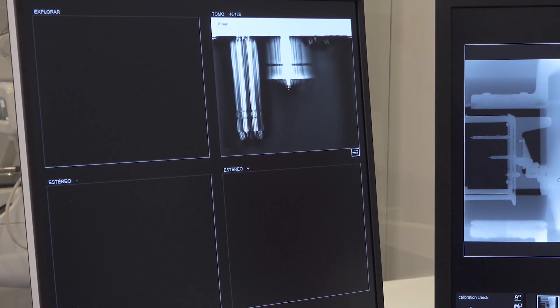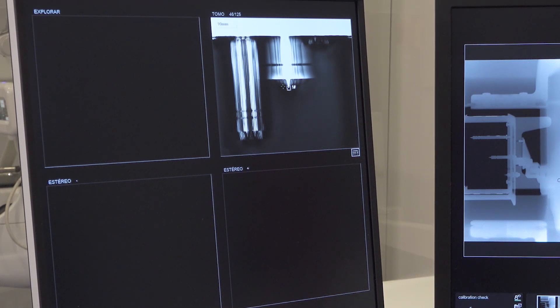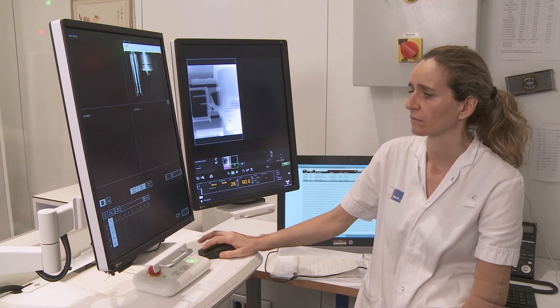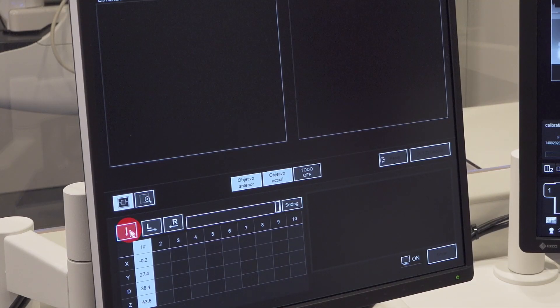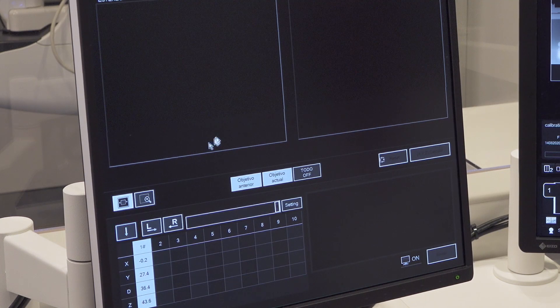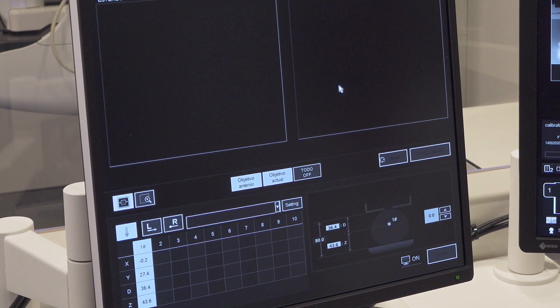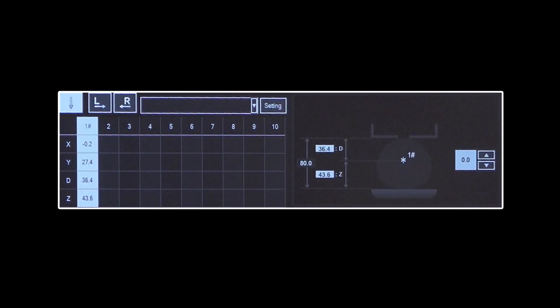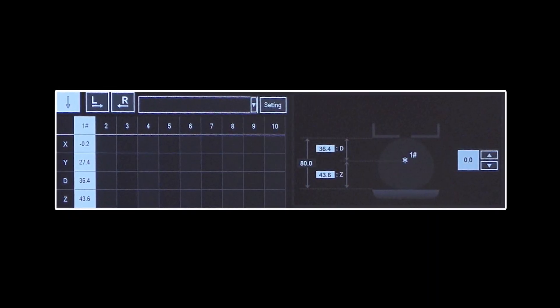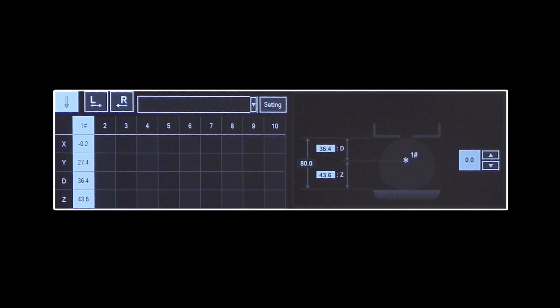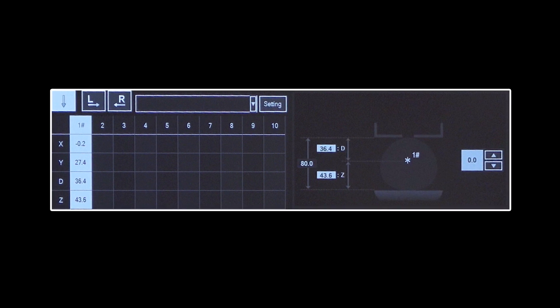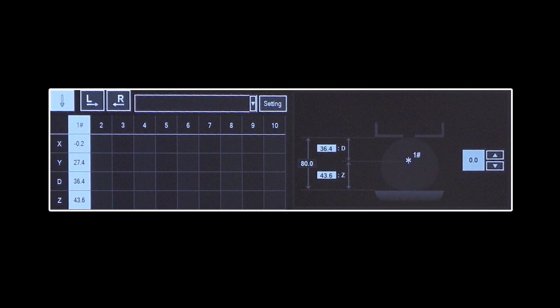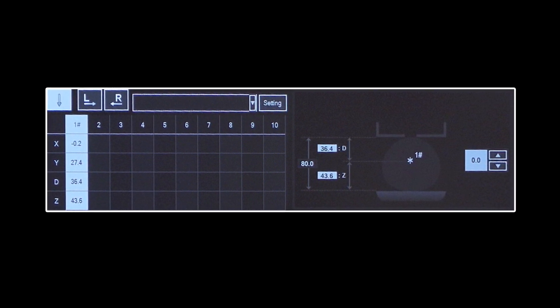Place the marker on the target. Select vertical approach. Observe the breast pictogram indications: breast thickness, target distance to breast support and skin, as well as the target coordinates X, Y and Z.